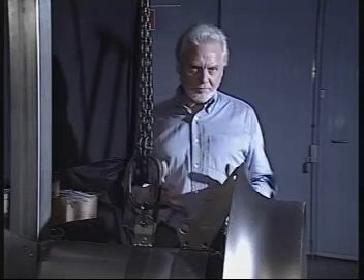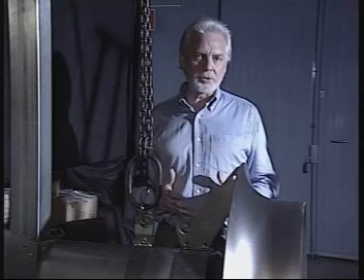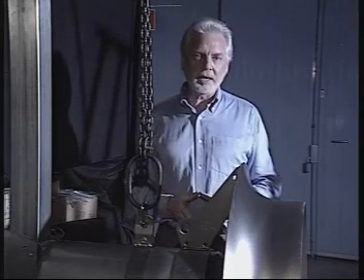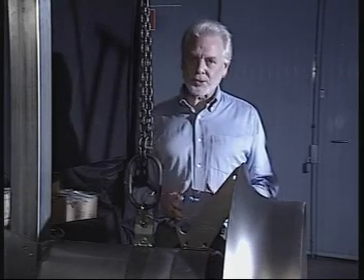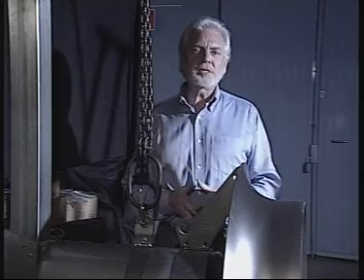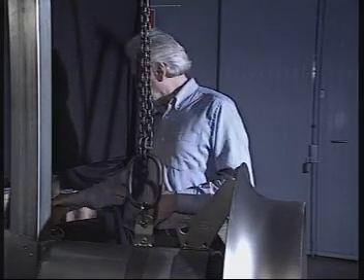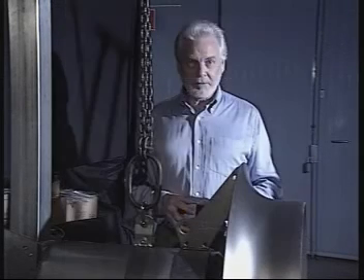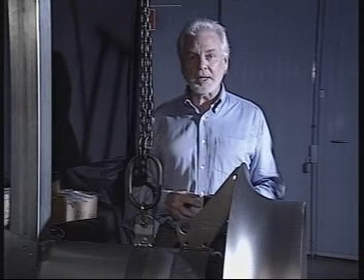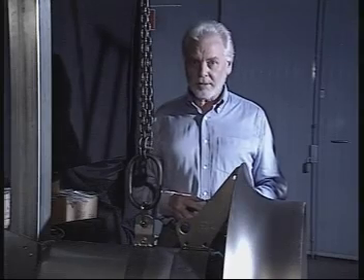The explosion-proof mixer is restricted to the use of thermal switches with or without FLS. The CLS is not explosion-proof and can't be used in this area. The sensors are monitored by the Flygt MiniCAS supervision relay and should be interfaced with your control panel. If the sensors to the supervision relay MiniCAS are not properly connected, the mixer may sustain damage.